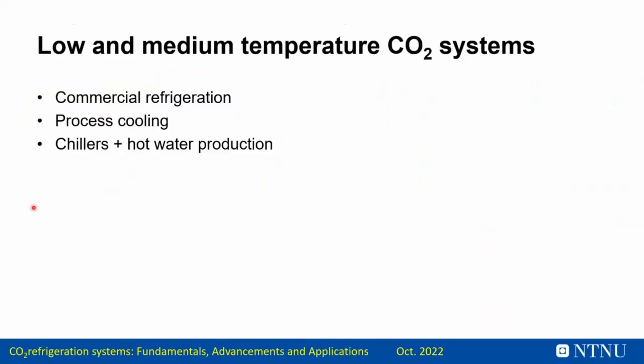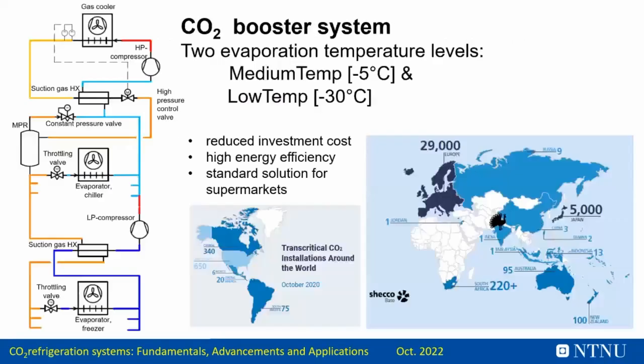Now let's have a look at low and medium temperature CO2 systems. I will go shortly into commercial refrigeration, process cooling, and hot water chillers. CO2 booster systems are currently introduced whenever a supermarket is replaced in Europe. Mainly they go for a CO2 system because of the very low investment cost and high energy efficiency, and for supermarkets in Europe and Japan it's a standard right now.